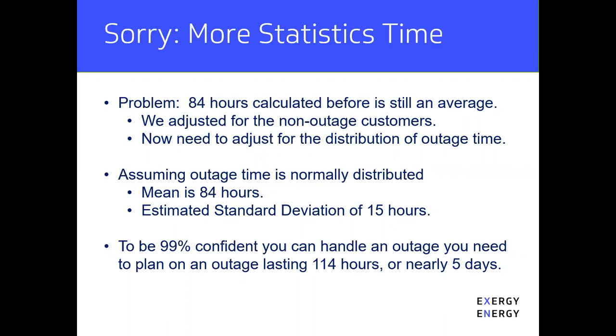I don't have a really good statistic, but if we assume the outage time is normally distributed with a mean of 84 hours, and we estimate a standard deviation of 15 hours, then to be 99% confident that you can handle an outage, you need to plan on an outage lasting 114 hours, or nearly 5 days. Is this unrealistic? Am I just making numbers up?